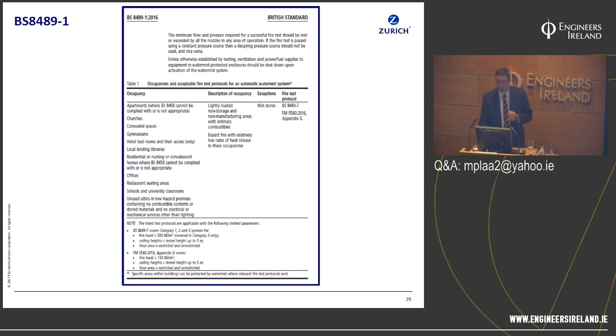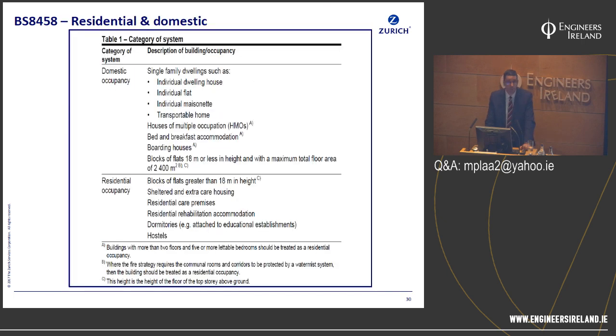Those would mostly, if it was sprinklers, be ordinary hazards, would they? They would, light or ordinary hazard, yeah. But there would be some slight exceptions which I'll cover. And if you're dealing with residential, which I suspect some of you are as well, so within the residential and domestic market, there's again, depending whether you're dealing with domestic or residential, there are some specific applications and occupancies. And again, it's to cross-map your building or proposed building with the list of occupancies on there to make sure you've got a fit. You're fitting a square peg into a square hole.